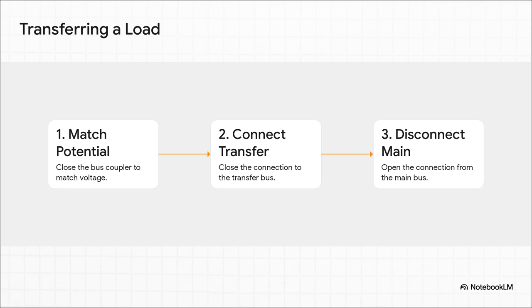First, you connect both buses together using something called a bus coupler. It's just a special breaker that links the two. This makes sure they're at the same voltage. Then, you close the connection to the backup transfer bus. And only after all that do you safely open the connection from the main bus. It's a completely seamless handoff. The customer never even knows it happened.